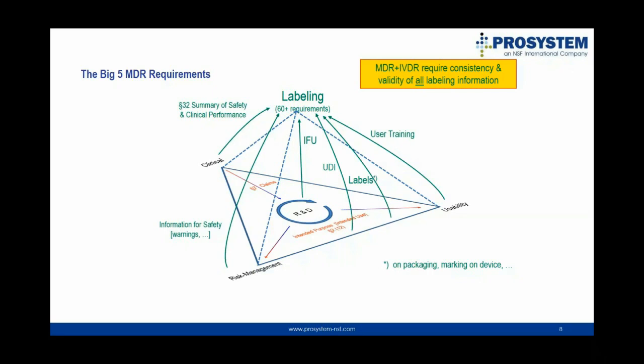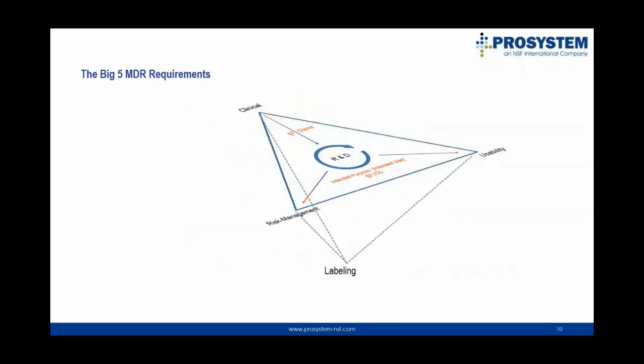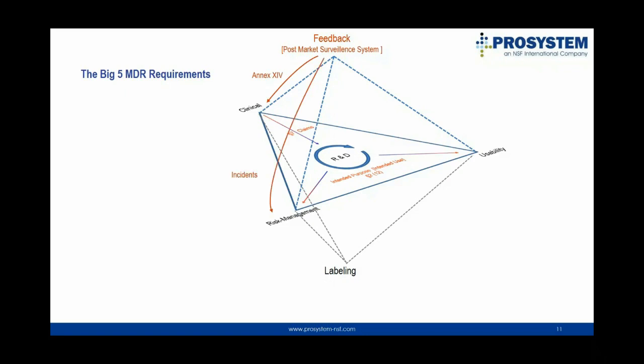Let's put this labeling on a visual basis now on the downside of this diagram and have space available on the top. And this space on the top is filled with requirements on post-market surveillance. Let me shorten this in the term feedback. It means all the information we can gain and collect from the market fed back to the manufacturer of the medical device. And in this context, we also have a majority of requirements we will hear more about by my subsequent speaker, Mr. Güler, who will introduce you in more detail what are the PMS requirements of the new medical device regulation.